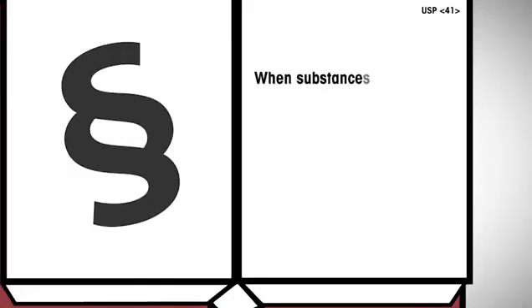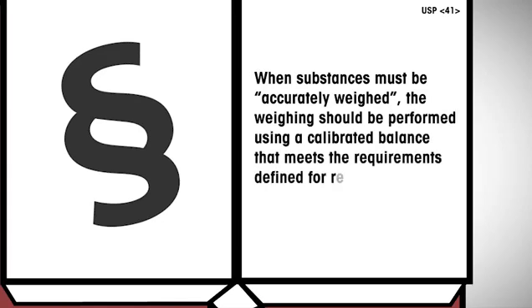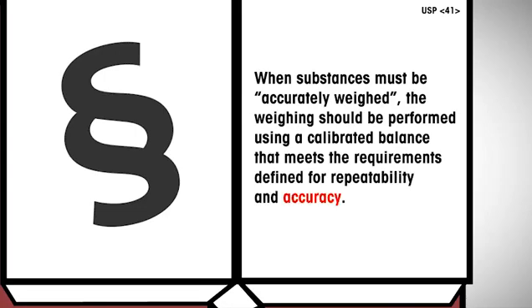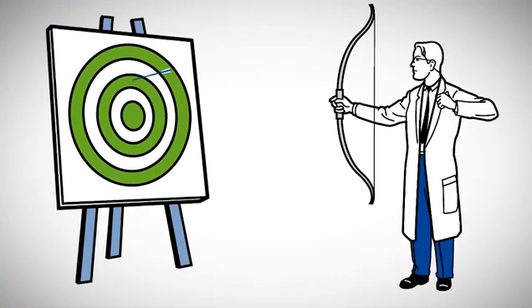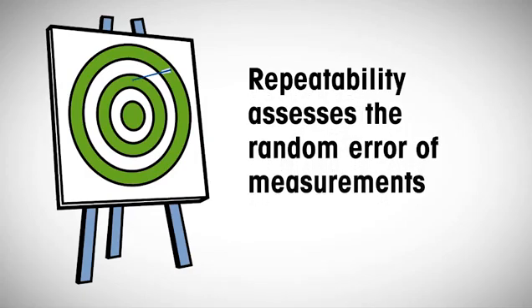USP 41 now also requires testing for accuracy. When substances must be accurately weighed, the weighing should be performed using a calibrated balance that meets the requirements defined for repeatability and accuracy. What's the difference between the two? Repeatability assesses the random error of measurements, or, more scientifically speaking, the closeness of agreement between values obtained by replicate measurements on the same object.